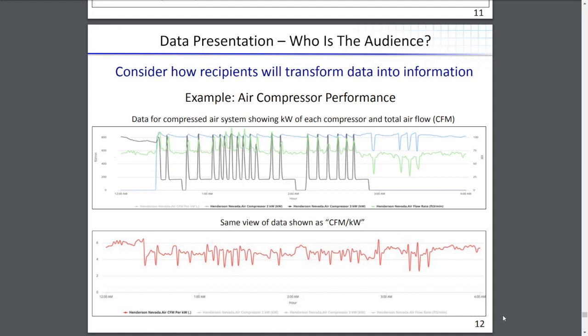The trend below is something that management may use. So this is a trend called CFM per kilowatt. And what it really means is how much air is being generated by my air compressors, how much energy is being used to generate that air. So it's a ratio between the two. And whether you have 1, 2, 3, or 5 air compressors running, that number should be about the same.